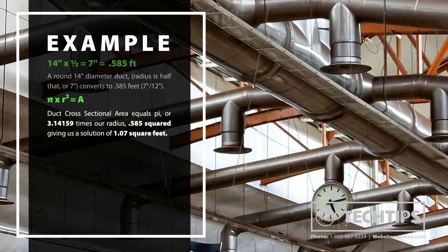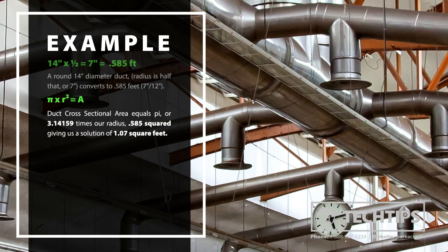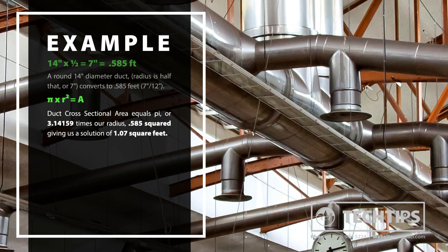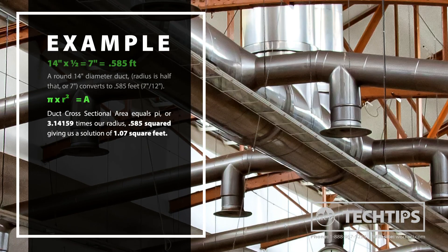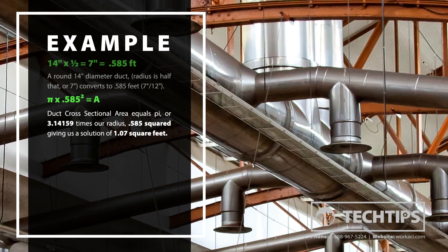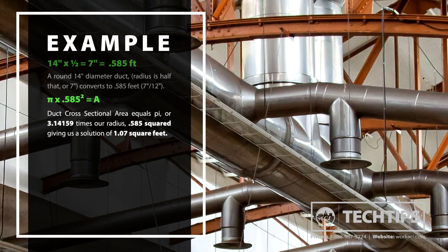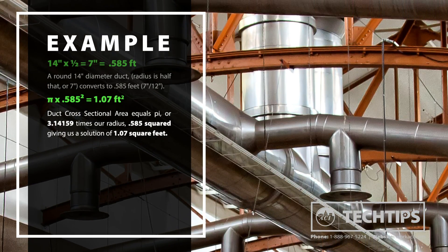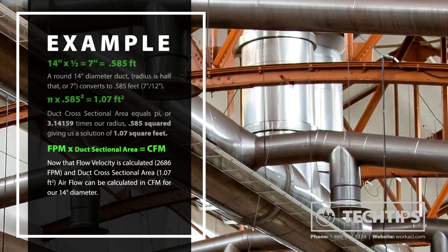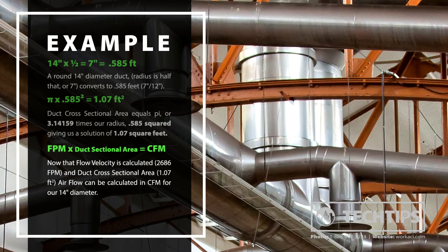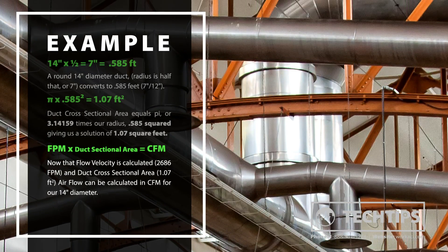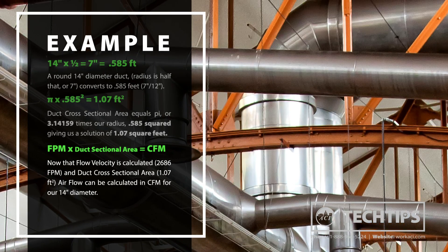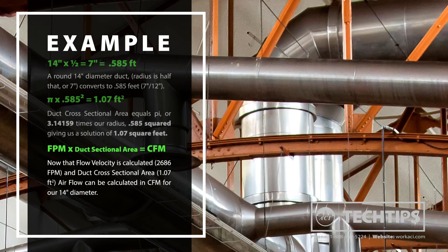Substituting our values into the equation, we see that the duct cross-sectional area equals pi, or 3.14159, times our radius, 0.585, squared, giving us a solution of 1.07 square feet. Now that we have calculated our flow velocity and our duct cross-sectional area, we can calculate airflow in CFM for our 14-inch diameter duct.